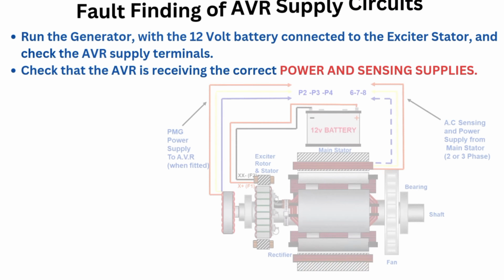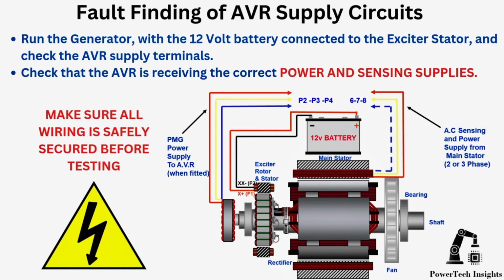Fault finding of AVR supply circuits. Run the generator with a 12-volt battery connected to the exciter stator, and check the AVR supply terminals. Check that the AVR is receiving the correct power and sensing supplies.